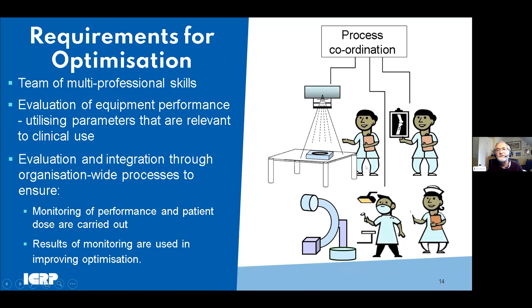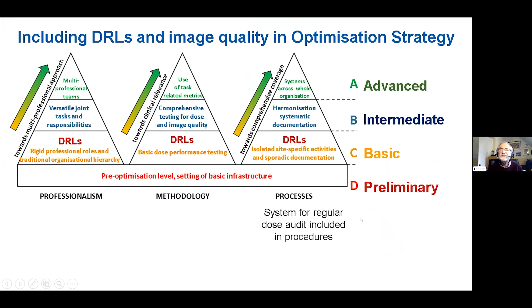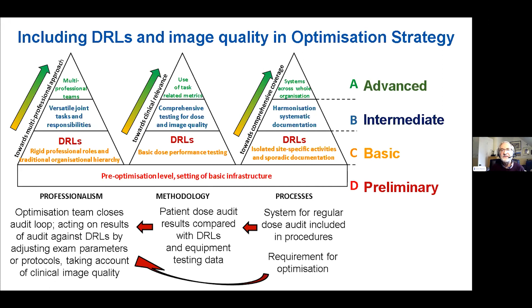So going back to our diagram again, the DRLs, as I said, fit in really at this stage as we're moving from level C to level B. So we have a system for regular dose audit in the procedures. The patient dose audit results are then compared with the DRLs and the equipment performance tests. And then the process requires that the optimization team closes the audit loop. So they're acting on the results of the audit against DRLs by adjusting the examination parameters or protocols, and taking account of the clinical imaging as well, in this gradual development and improvement.